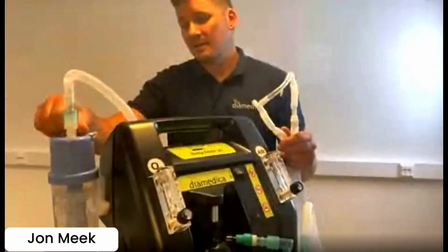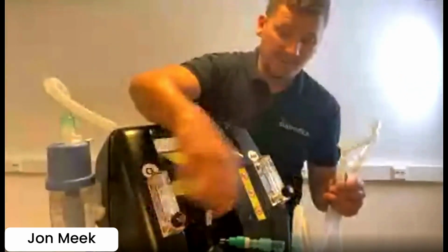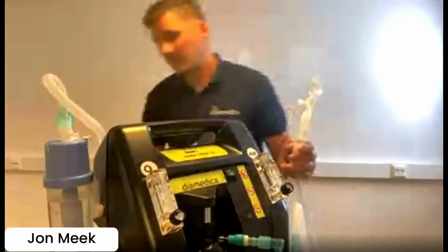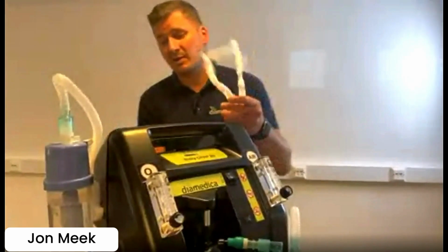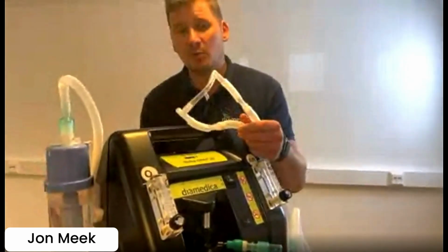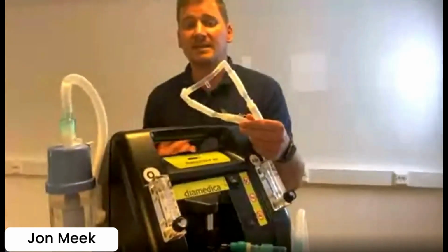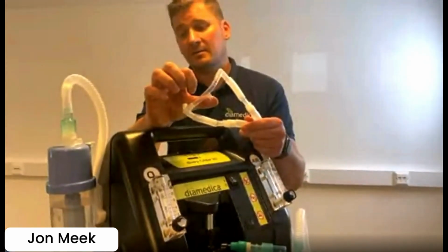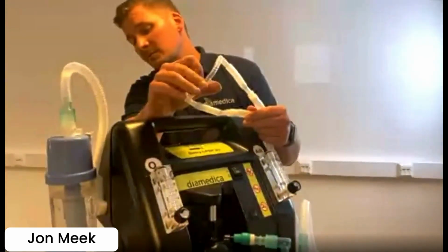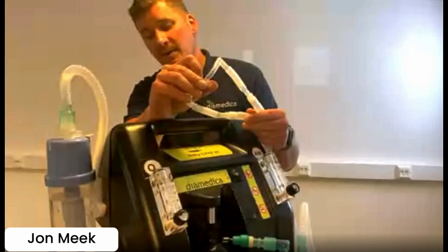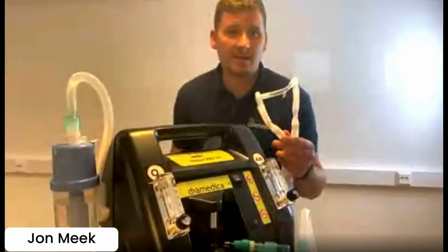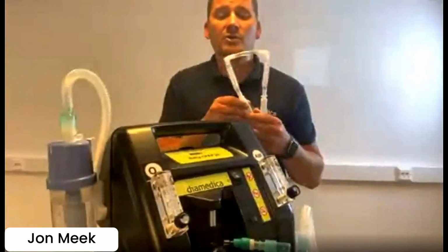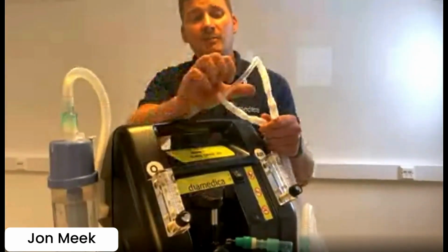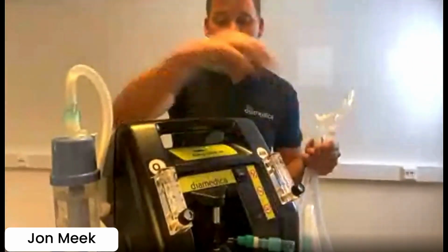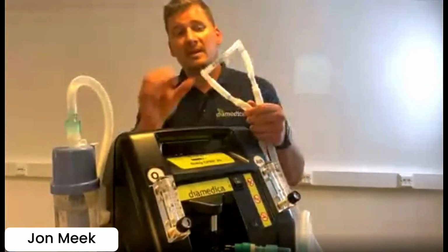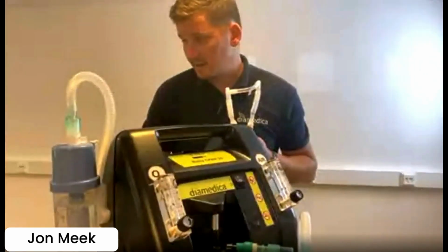But it also means the cannula might not be fitted correctly. So if I reduce the flows, as you can see, there's no pressure generated in the bubble bottle. So CPAP is not being provided to the level that we set it to. If I occlude the cannula, you'll see bubbles are now being generated. It's not because there's a leak, it just means you haven't got a good connection on the nasal prongs for the infants. So it's really important, instead of just increasing the flows until you get bubbles, to make sure that the nasal prongs are fitted correctly as well.